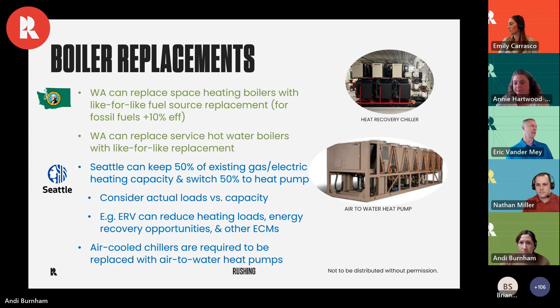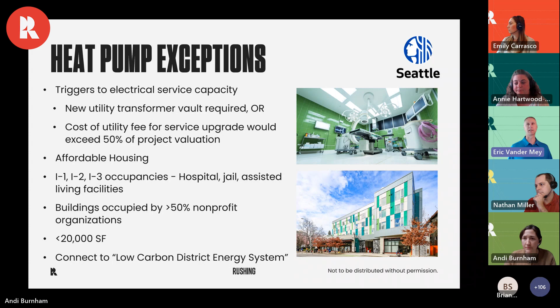The other provision for Seattle is air-cooled chillers are required to now be replaced with air-to-water heat pumps. There are some exceptions, but buildings that have both heating and cooling going on, we're looking to replace those air-cooled chillers with air-to-water heat pumps. There are lots of exceptions to the base rules. As always, you can comply with the new code and fully move that direction, but there's a list of exceptions, including connections to low carbon district energy systems or other things that may be exciting for what's going on in your neighborhood of existing buildings.